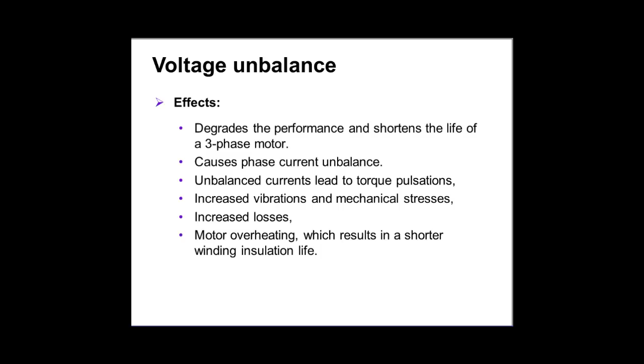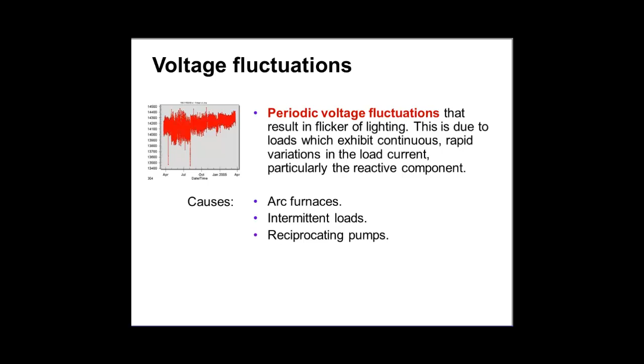Again, worse than that is periodic voltage fluctuations. If that happens, your system is absolutely unreliable. Causes: arc furnaces, intermittent loads, reciprocating pumps. Impacts: lighting flicker, maloperation of electronic equipment, maloperation of sensitive loads. These days, your life, my life, everyday life, fortunately or unfortunately, in the 21st century, is based on electronics and digital technology and computers, server computers, LAN and WAN and communications and routers or something.